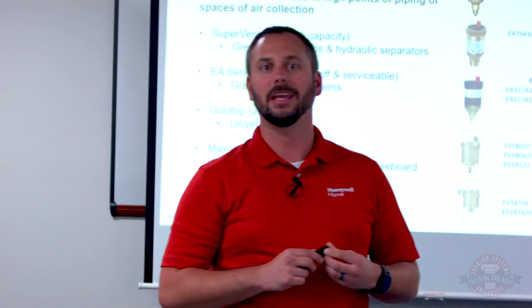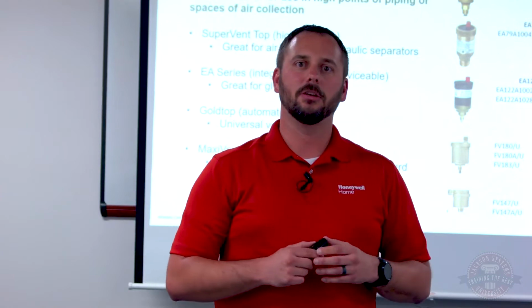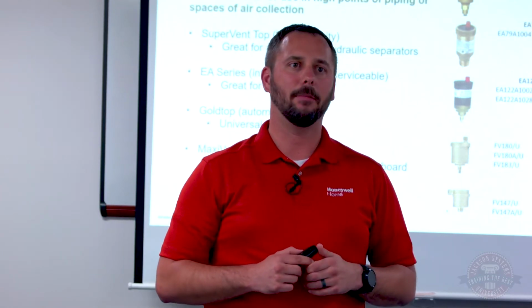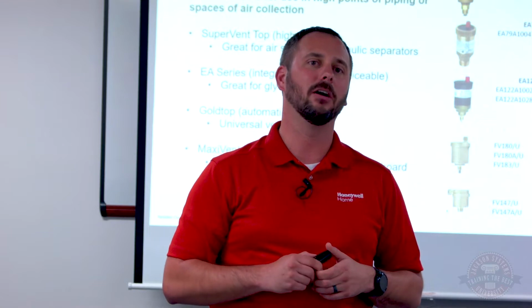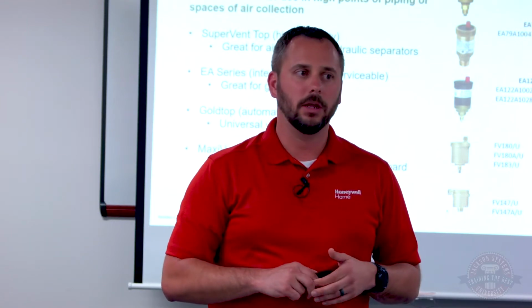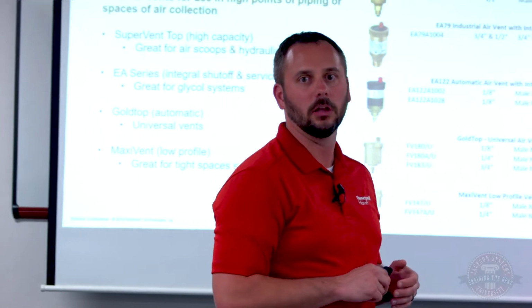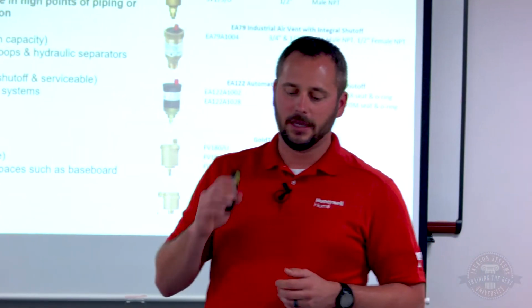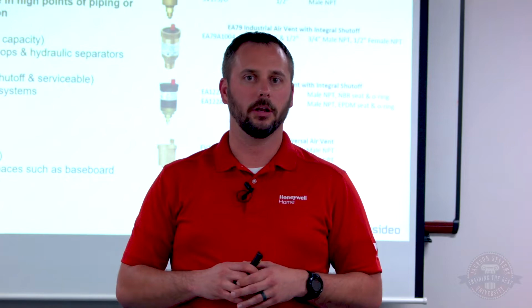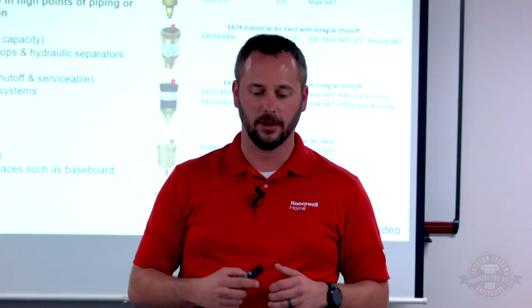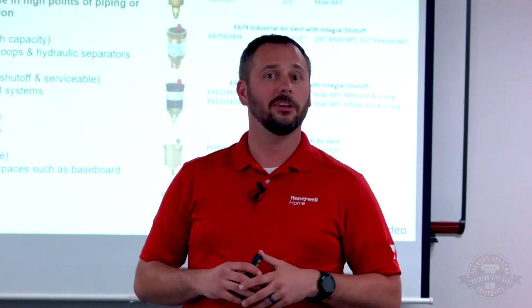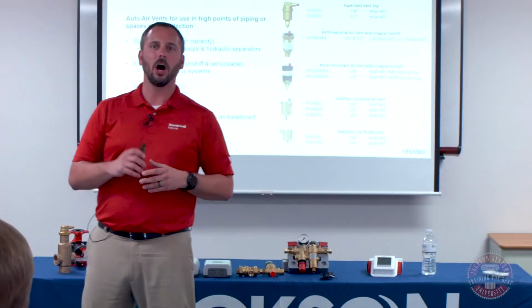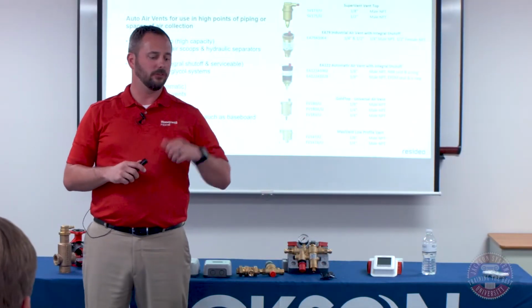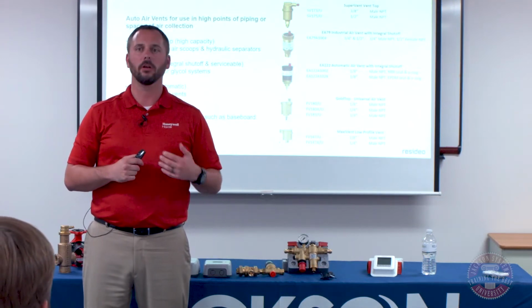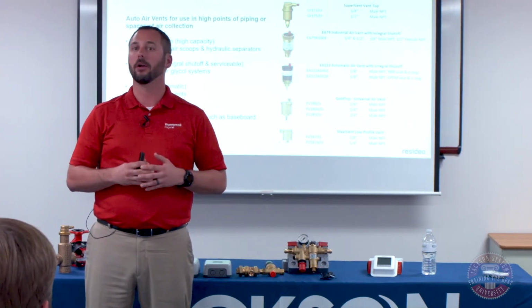So very unique. We sell a tremendous amount of those in Canada because, as I had mentioned, the main reason being glycol has a really bad habit of leaking out where water won't. And in Canada, because of their temperatures, they use a lot of glycol. So that little 1/8-inch EA vent is incredibly popular in Canada because of the ability to shut it off and service it. We have just basic universal vents too, so nothing real fancy, but all of them have a float assembly inside of them. And then we also make a low-profile vent that's good for baseboard, tight applications, areas where you don't have a lot of room.